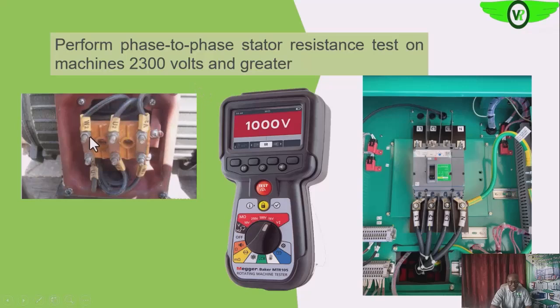Then you probe between W1 and W2, and then V1 and V2. Since the windings are the same, you expect that the resistances should be the same. If there are variations, the variations should not be more than 2 or 3%. If there are variations, that means something heinous, something dangerous is happening within the windings. So you need to check that out.